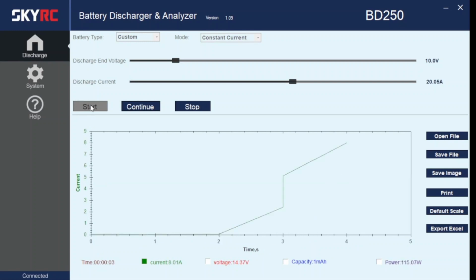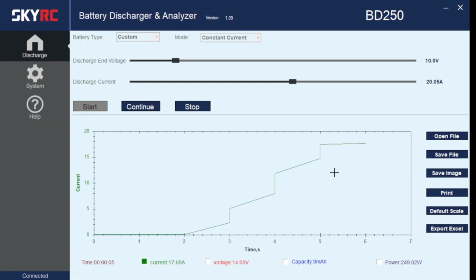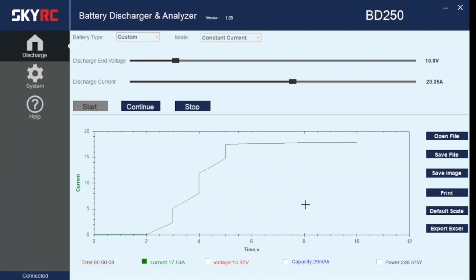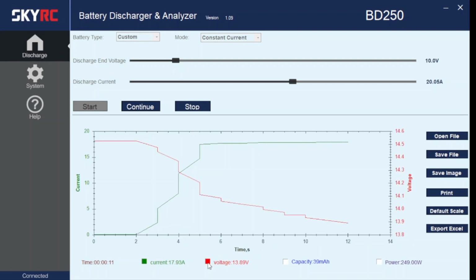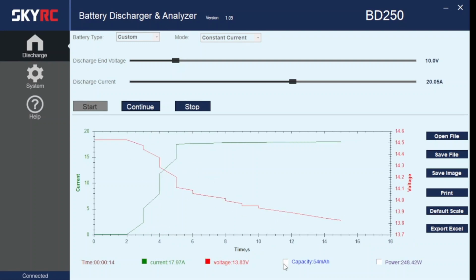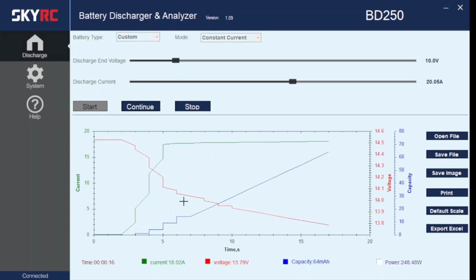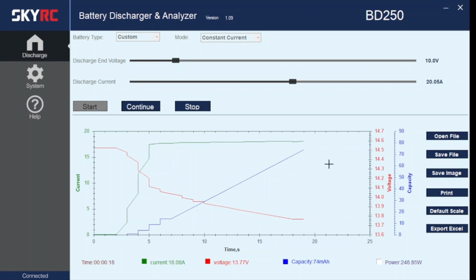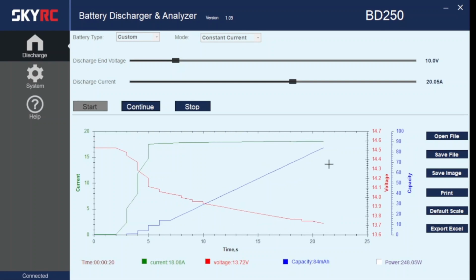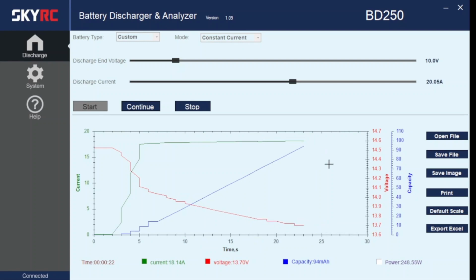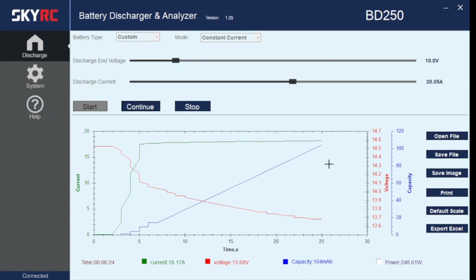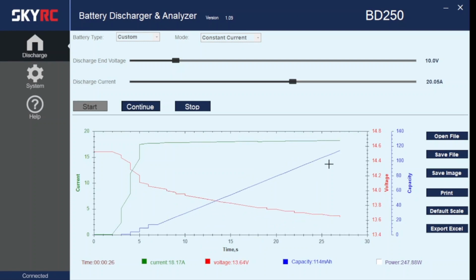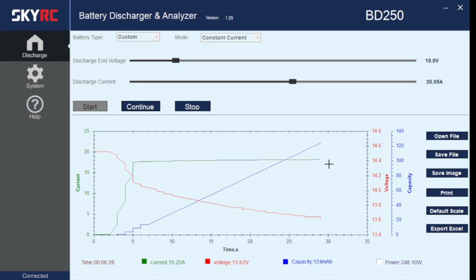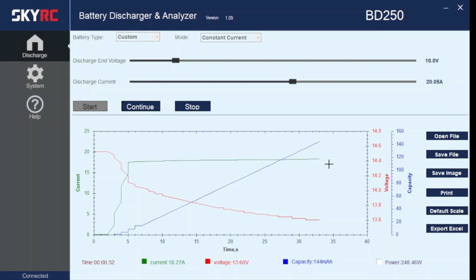So this is now starting the discharge test. That's the current going up, sitting at about 17.8 amps at the moment. You've got your voltage chart as well, it'll slowly start to go down, and you can get your capacity that goes up too. We'll let this discharge—this should take about 6 hours, give or take. We'll come back after that and see what we finally get out of this Invicta battery. Cheers.